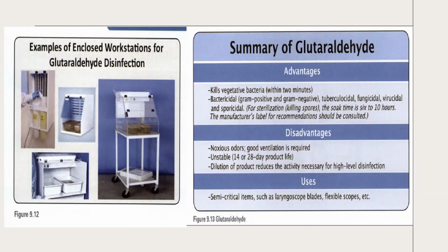if it should be able to kill a spore, which means sterilization, then 10 hours are required. But the point is, who wants to wait for 10 hours? That's another question. So if the instrument is something that can be sterilized in a low temperature sterilizer, not high, low temperature, then that's an option anyway. But at least it has the claim and verification, that validity, that it can be sterilized. Then, of course, always go with the manufacturer's recommendation. Not just others. Good ventilation is required.